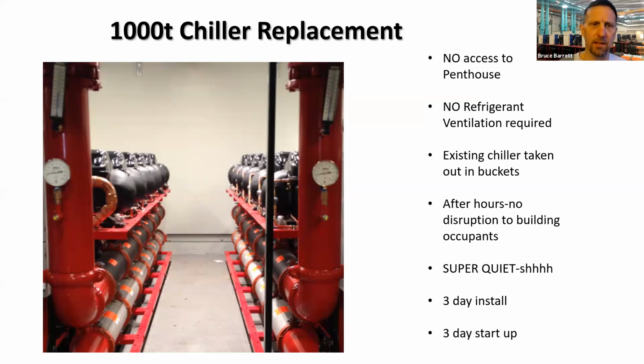Super quiet installation. There's now panels on these. You cannot hear the compressors run. All you hear is pumps. This low refrigerant charge, we dropped it almost a fifth of the existing charge. They were able to get tenants that would get LEED points given the amount of charge in the mechanical room. So that was an unforeseen bonus, dropping the refrigerant charge.